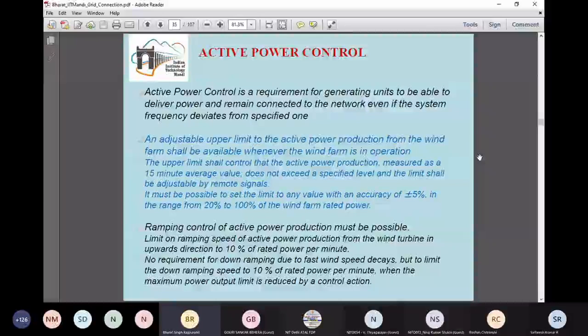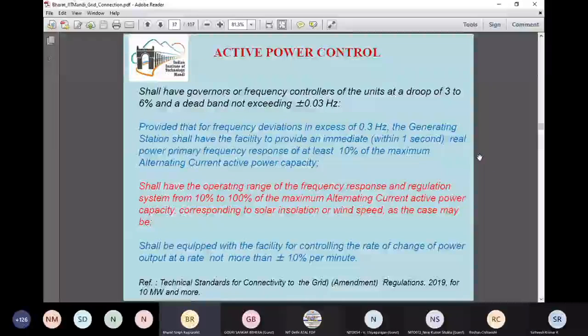For the fast down regulation, it is mentioned that power should be backed down from 100% to 20% in less than 5 seconds. So there are many such reduction ramping controls prescribed in the Indian electricity grid code. Fine. If you see the reference part, it is from this regulation which is available at the Central Electricity Authority CEA website. You may also refer to the Technical Standards for Connectivity to the Grid Regulations 2019 for wind farms of 10 megawatt and more.